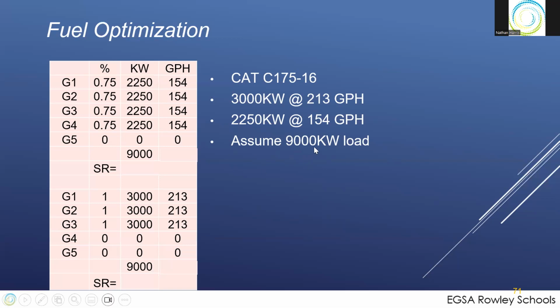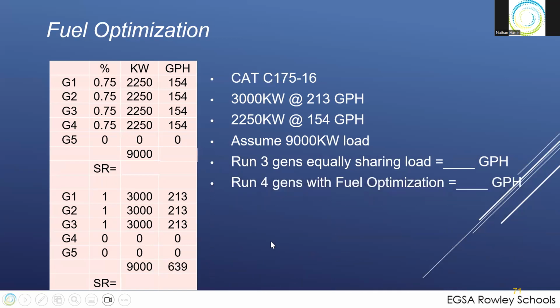But if we assume a 9,000 kW load, you can achieve that with 3 generators, all running at 3,000 kW, 3 times 3 being 9,000 kilowatts in this case. On this machine, you can also achieve that by running 4 gens at 2,250. What's the difference? Well, first of all, if you run 3 gens equally sharing load, your gallons per hour is 639. You run 4 gens with fuel optimization enabled, you're running a total of 616 gallons an hour. Okay, not a big difference.